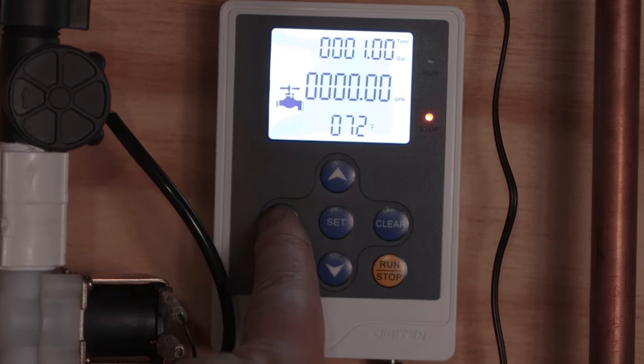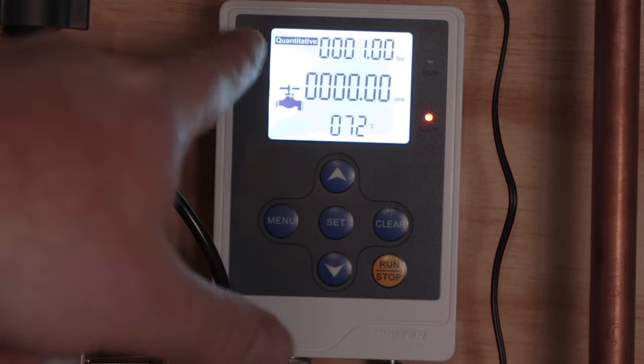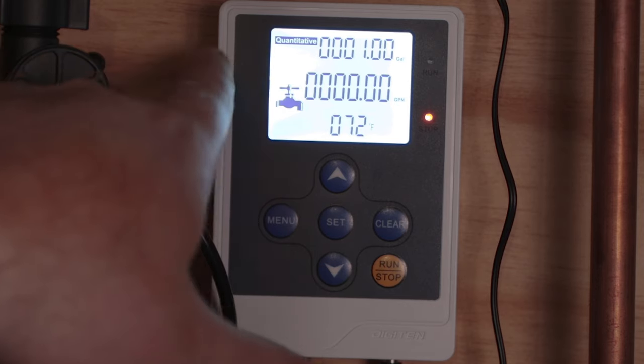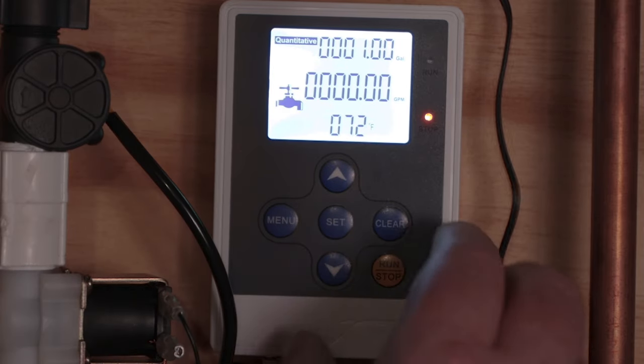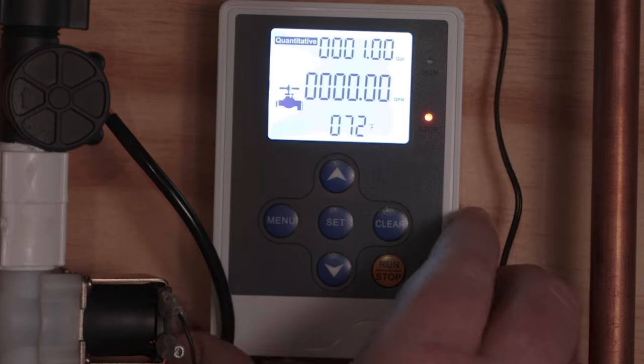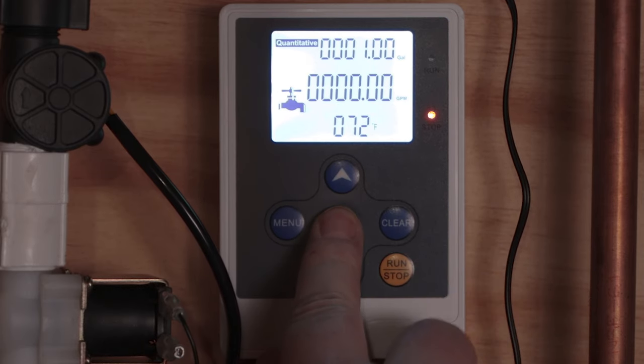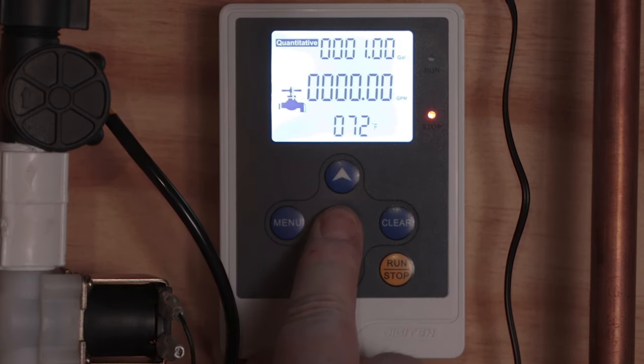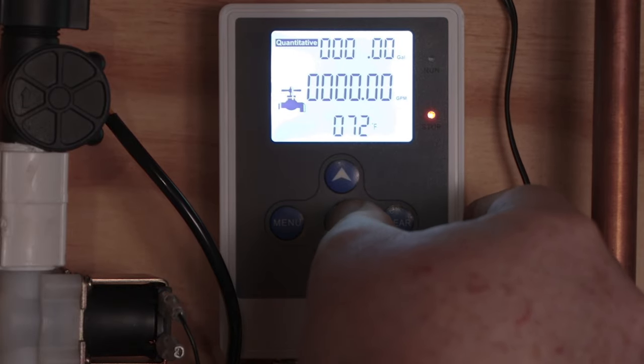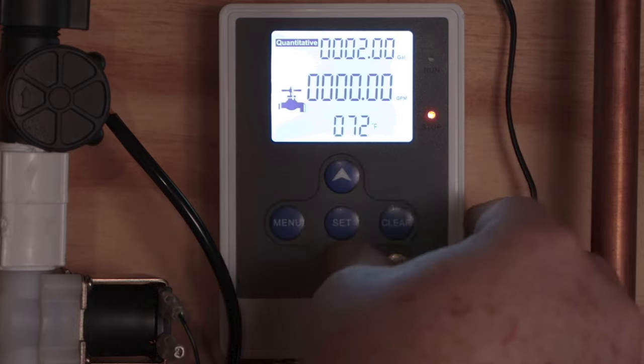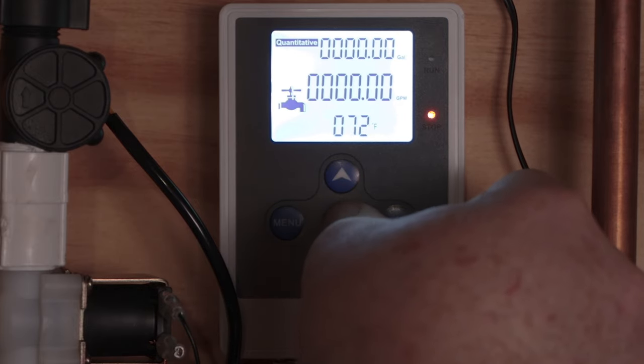So there's a few different options. The main one that I am interested in is this quantitative. So basically, whatever you set this figure right here to be, that is what the amount of water that the system will let flow through. So how you do that is you just press the set button, hold it down until you see the numbers start to flash. And then you can set your figures by using the up and down arrows. So right there is zero.